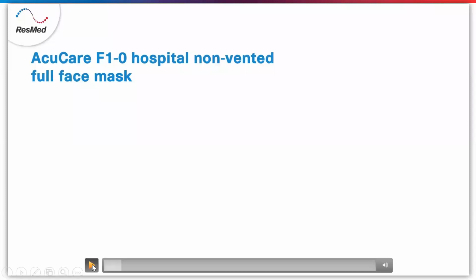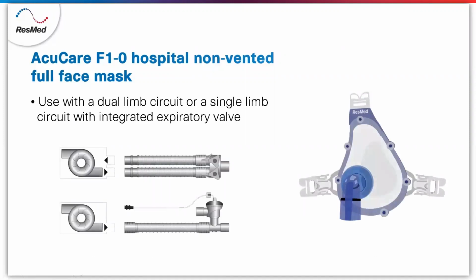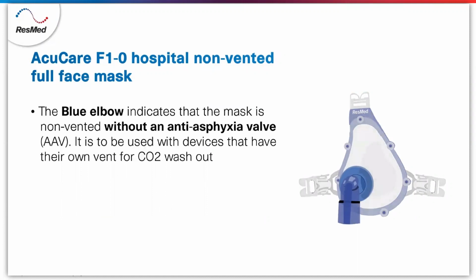AcuCare F1-0 Hospital Non-Vented Full Face Mask. This mask is meant to be used with a dual limb circuit or a single limb circuit with integrated expiratory valve. The blue elbow indicates that the mask is non-vented without an anti-asphyxia valve. It is to be used with devices that have their own vent for CO2 washout.